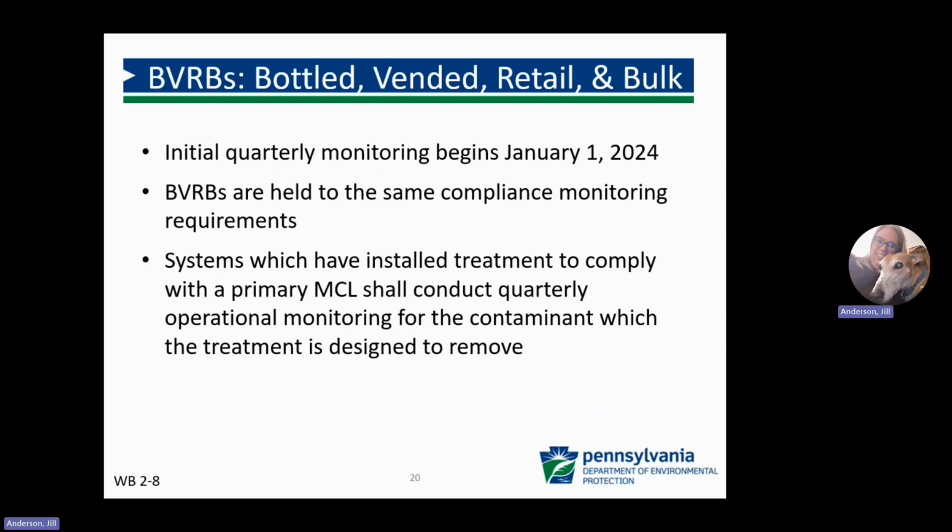Bottled, vended, retail, and bulk, or BVRB, water systems also have to comply with PFAS monitoring and compliance. BVRBs are held to the same compliance monitoring requirements, and initial quarterly monitoring begins January 1, 2024. And systems which have installed treatment to comply with an MCL shall conduct quarterly operational monitoring for the contaminant for which the treatment is designed to remove.